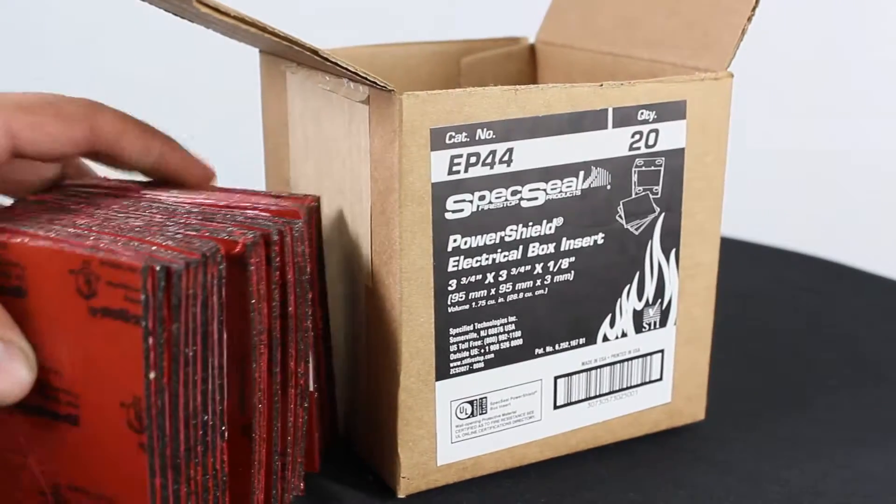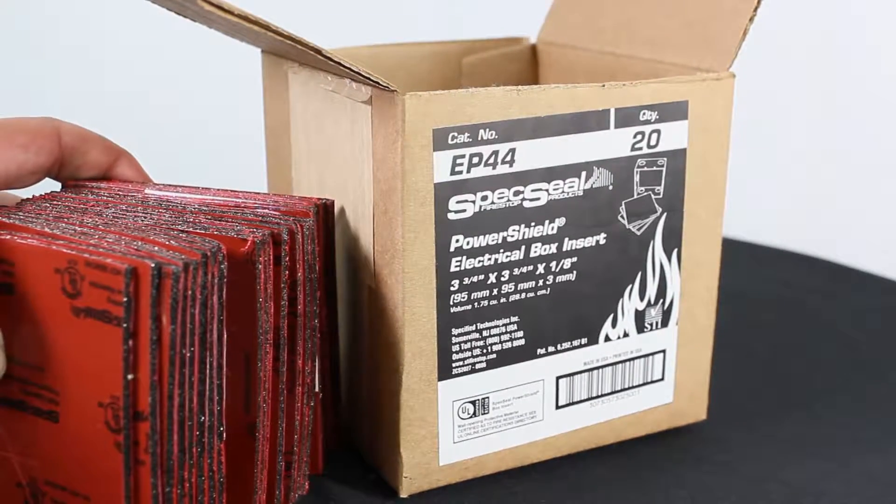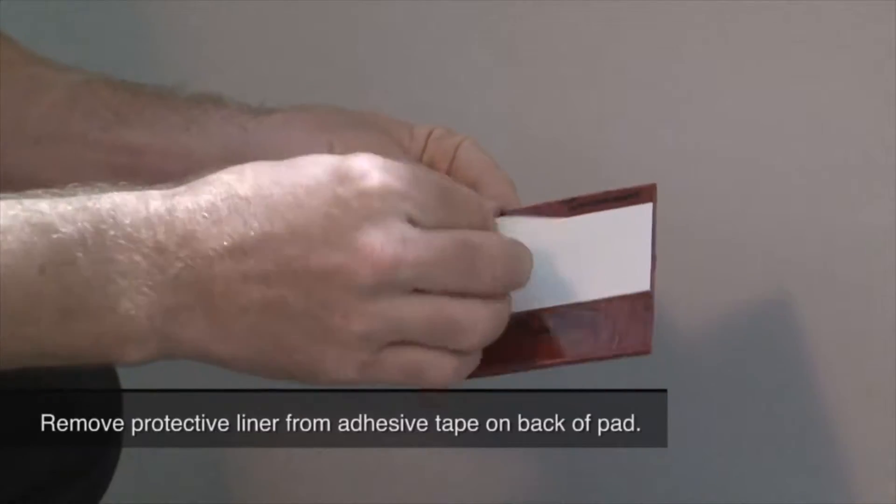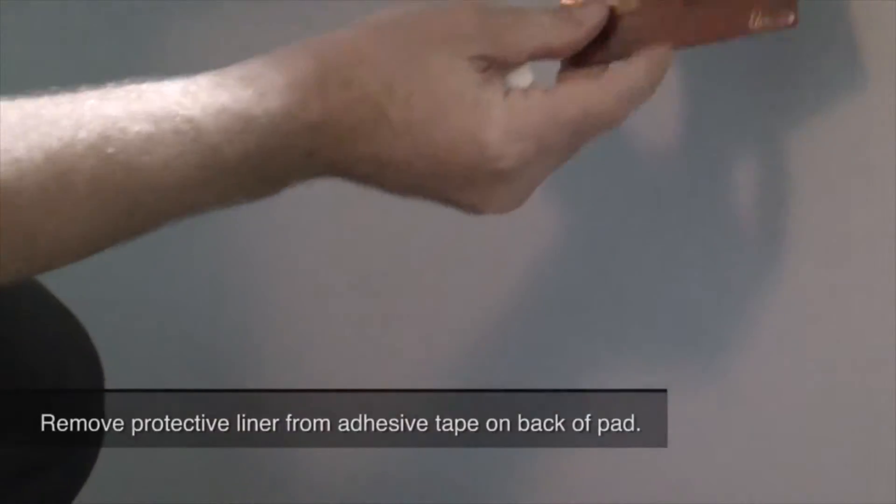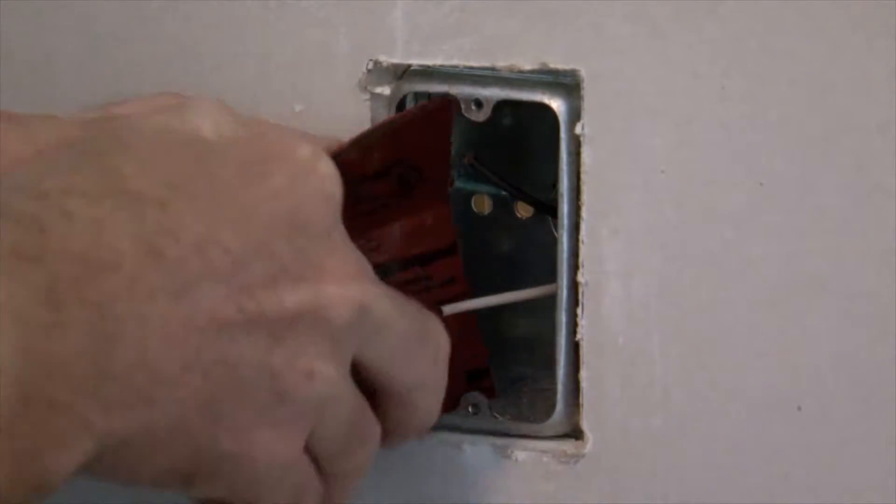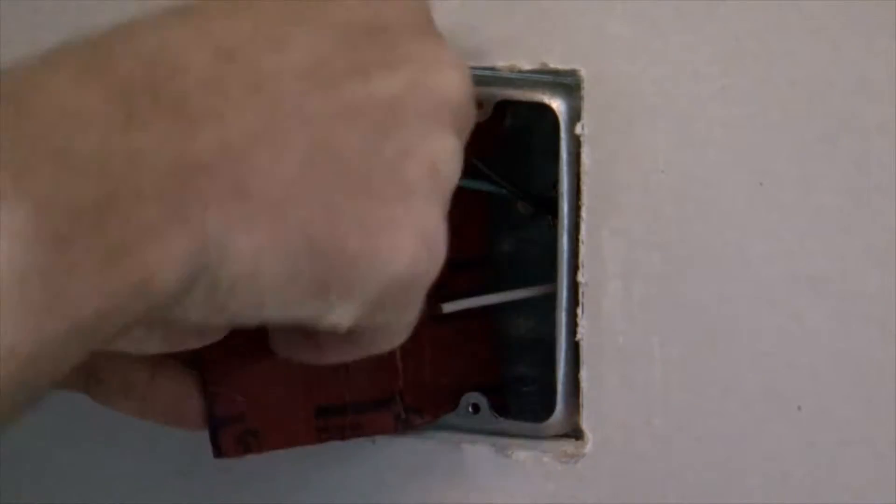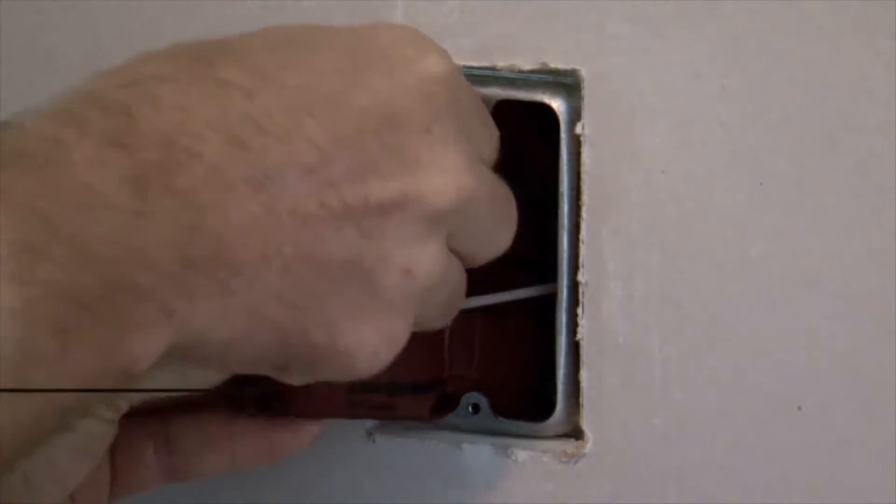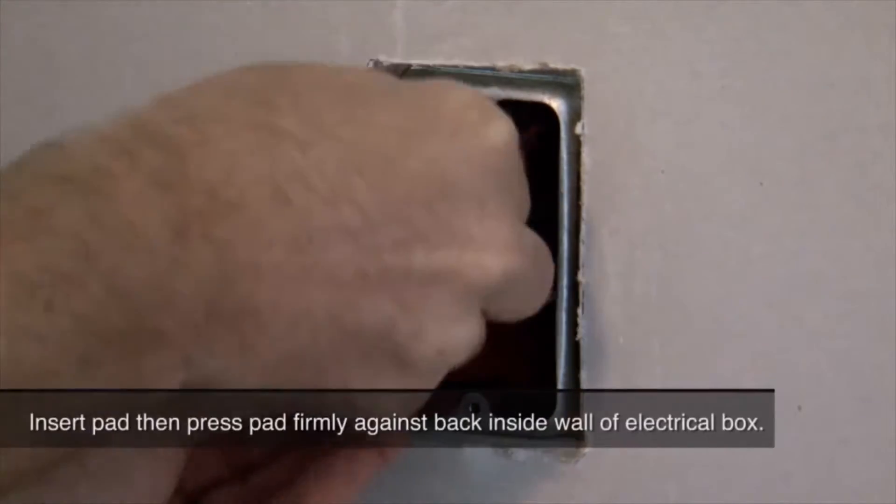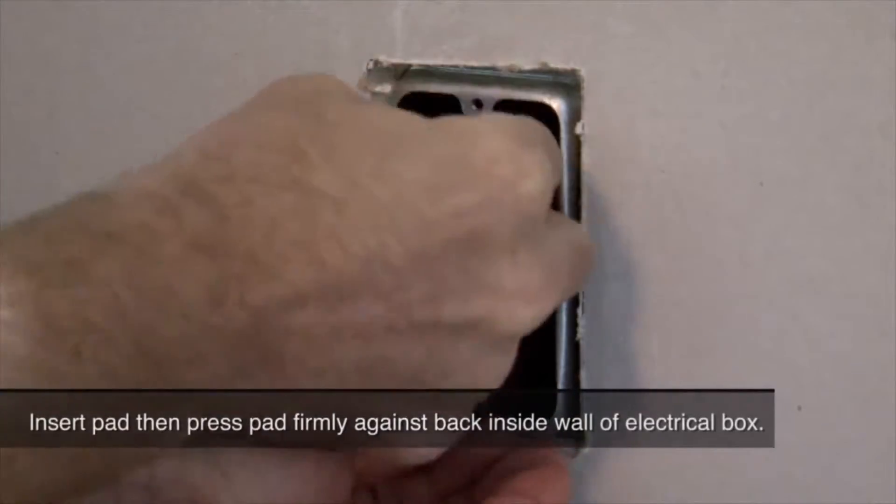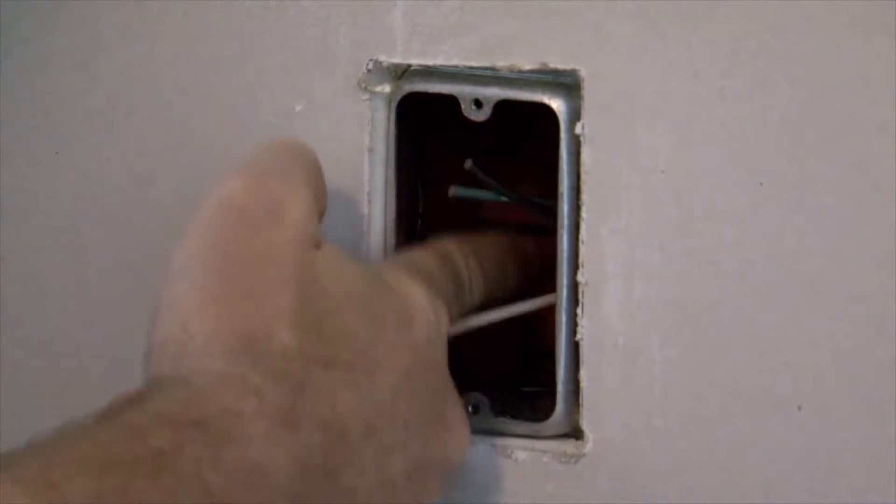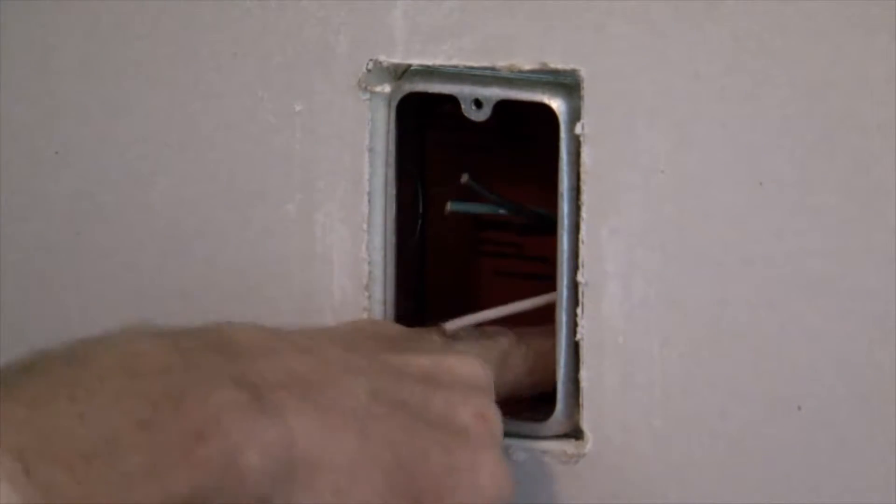switch or receptacle boxes. The insert has been designed to install inside the box directly against the back wall. The insert expands a minimum of 24 times its original size when exposed to high temperatures or flames, requiring no tools.